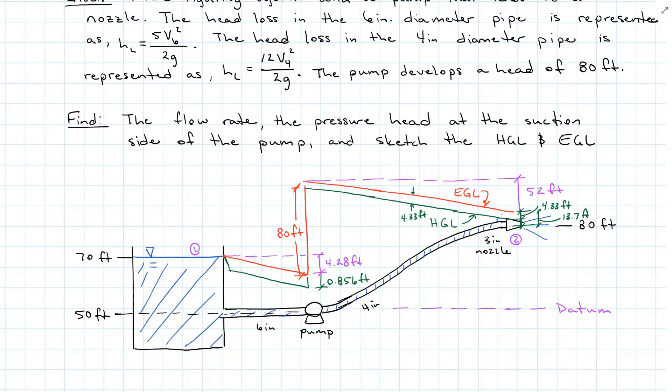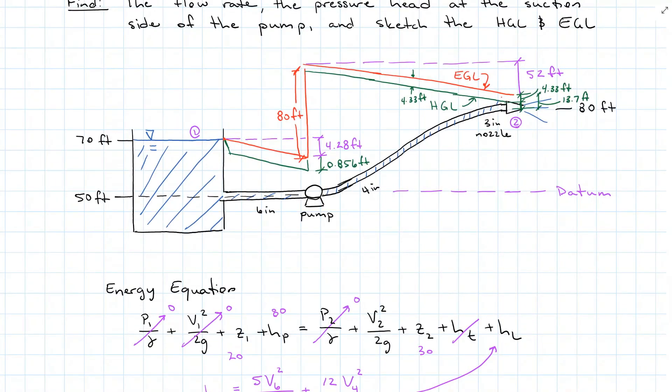We have our flow rate. So the very last thing we want is the pressure head at the suction side of the pump. So the pressure head is going to be this value right here before we get into the pump. So that's going to be the difference in height from the water elevation to the pump elevation. So we've got 20 feet there. And then we need to subtract that head loss of the 6 inch pipe, 4.28 feet. And then we also subtract the velocity head of 0.856 feet. And that gives us a pressure head of 14.86 feet.